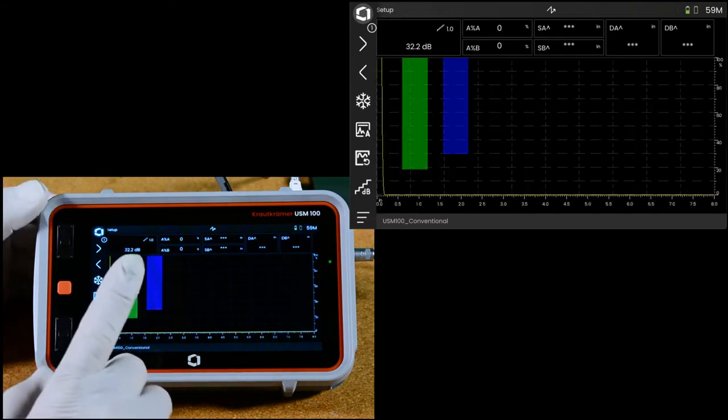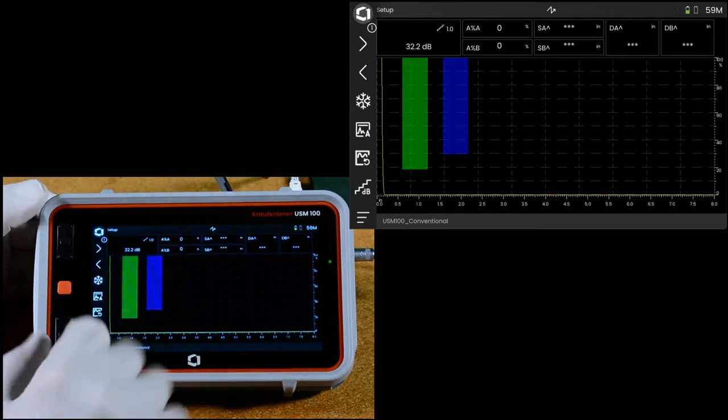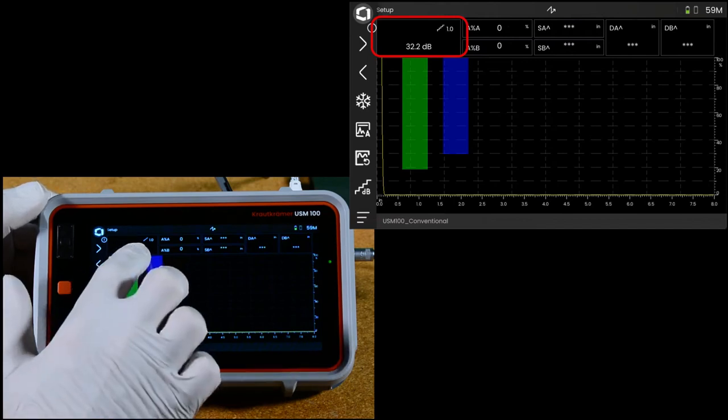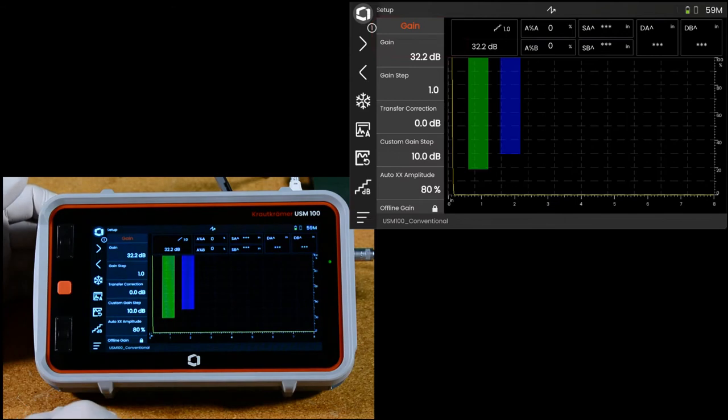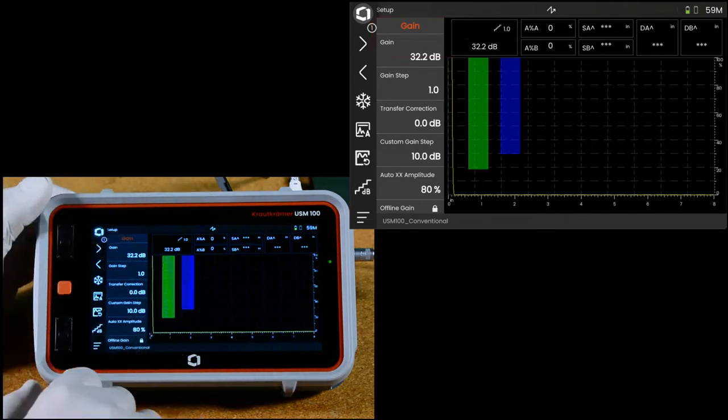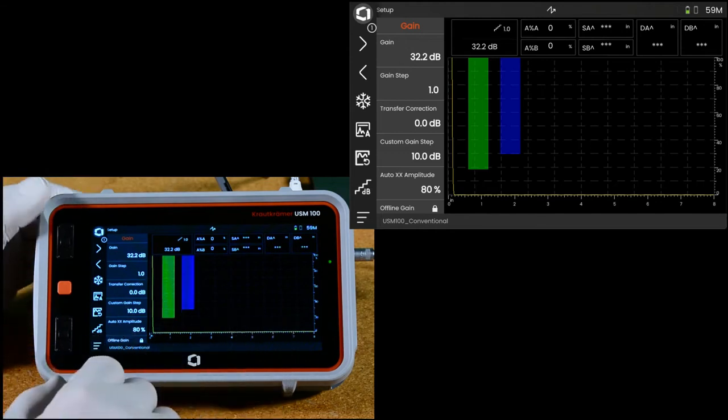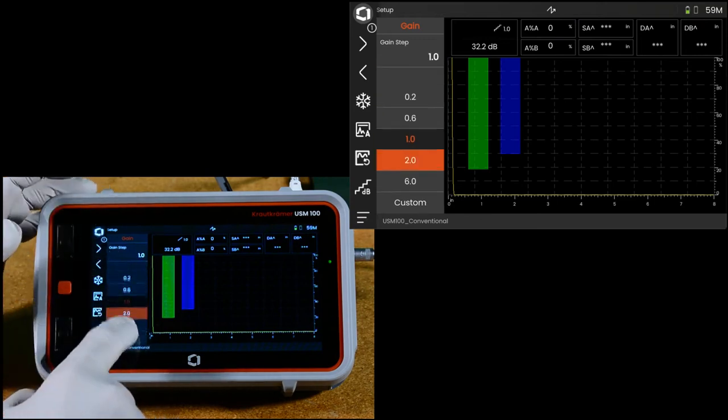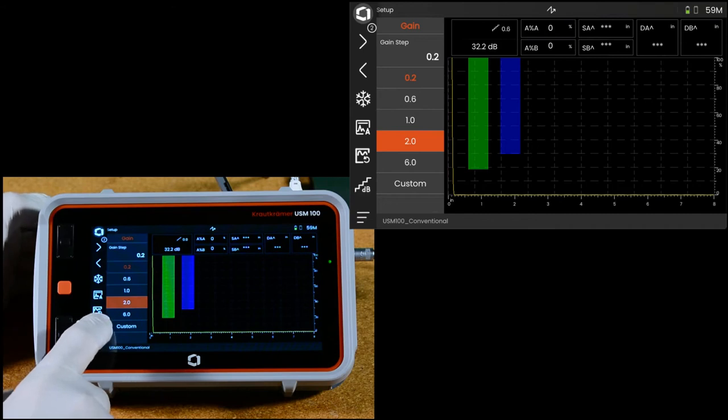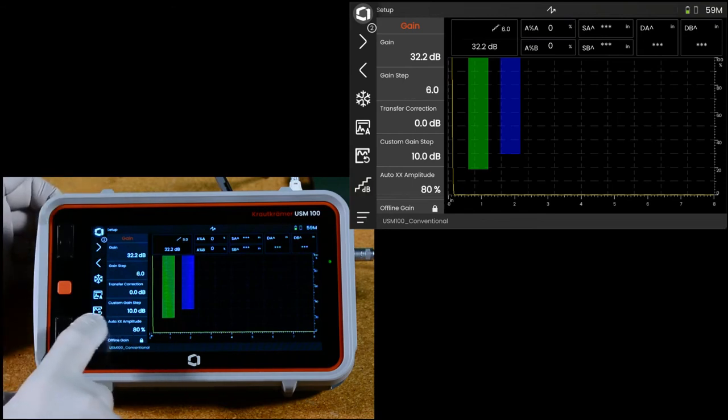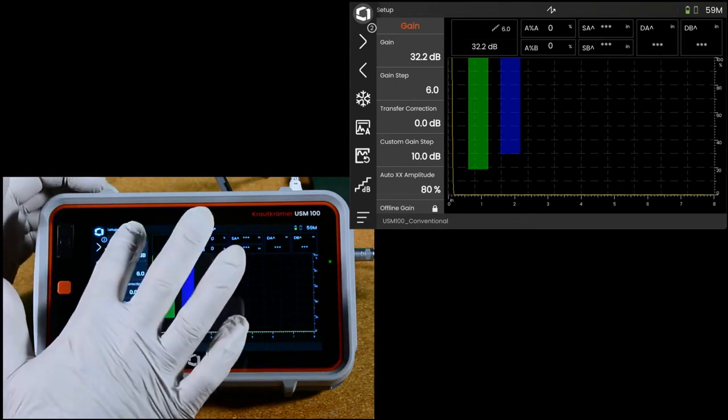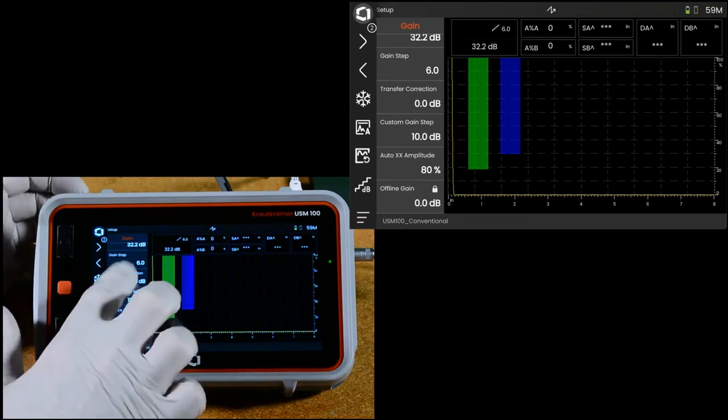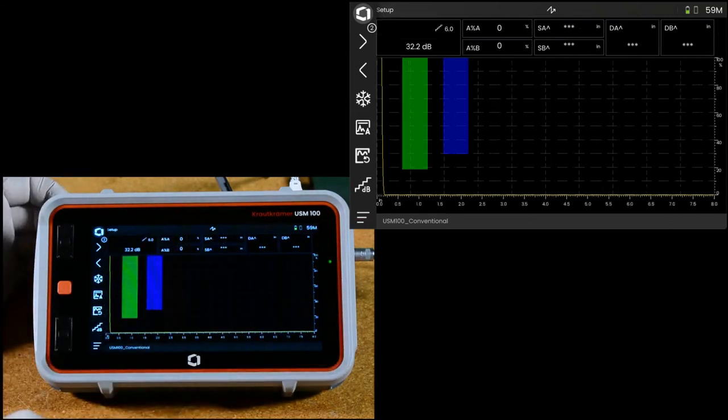Another special menu that is available at all times is the gain menu. Notice the gain control is prominent here in the upper left corner. If I touch the gain control, it opens a gain menu, a collection of things that are specific to gain control in the instrument. Here again is our gain step. So I can select that directly or I can hit the dB step over here on the, let's close that back to there. I can also adjust dB step using the dedicated icon on the command bar. Transfer correction, other gain pertinent items are on this menu. Close that by just hitting the gain control another time.